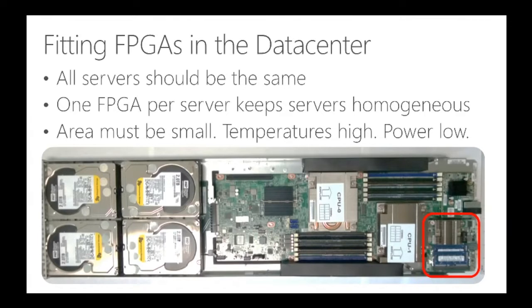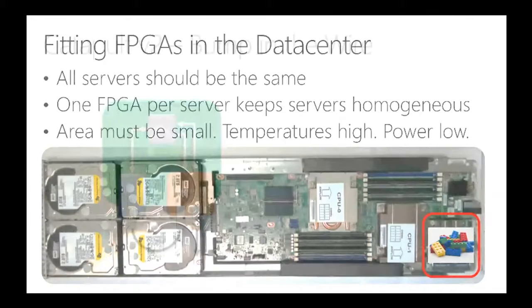And it turns out that this is the direction of airflow. That CPU heats up the air. That one does too. By the time the air gets to the FPGA, it's 70 degrees C. If your cooling air is 70 degrees C, you're definitely not going to put a 300-watt device in the back of that server. You're going to be melting everything behind it. So unfortunately, it's nice, but that's a tiny little pile of Legos. There's not that much you can build. If you ever get one of those in your stocking, there's like 12 Legos to it. Not too many designs you can make.